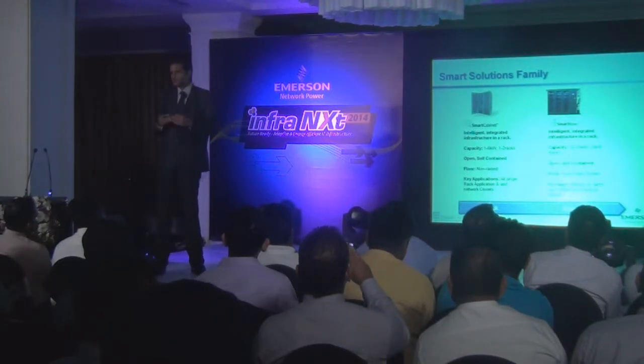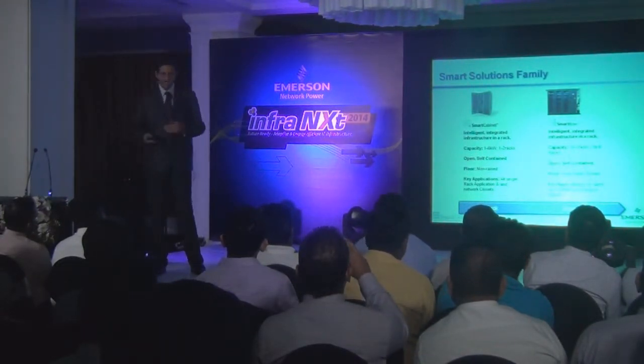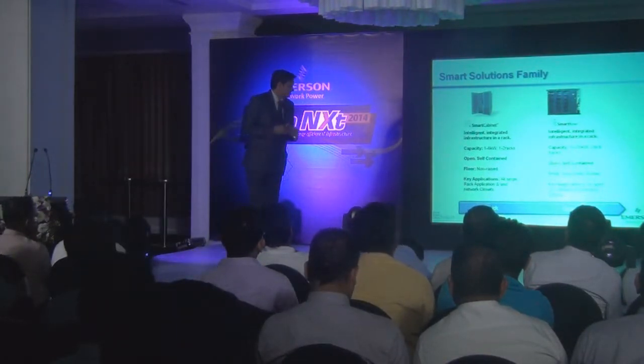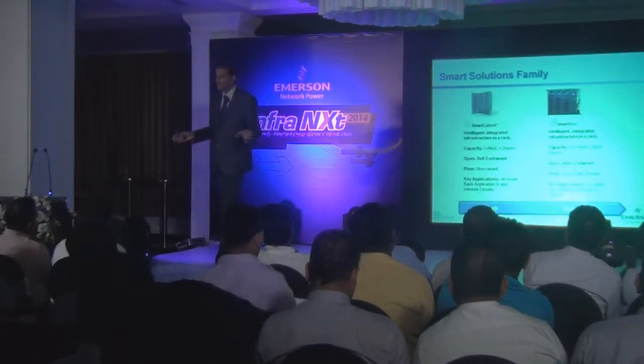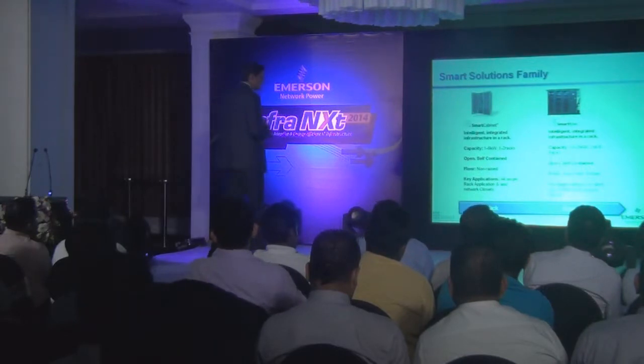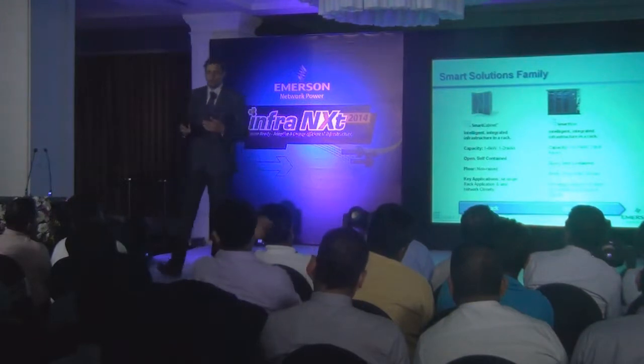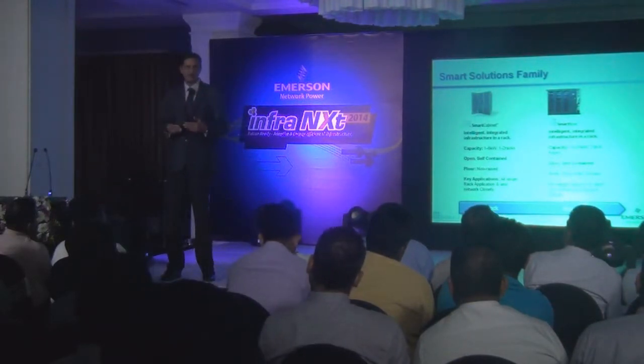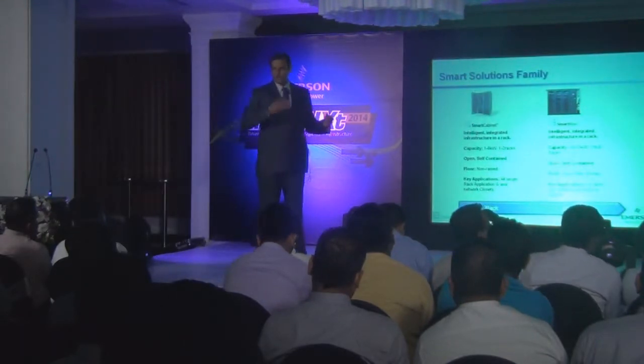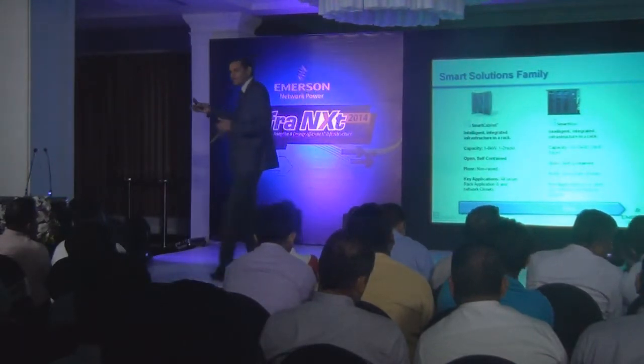It's a combination that starts from 3 and goes up to 6, and can be used in a very modular way. Here too, cooling is open and self-contained, and you don't need a raised floor since cooling is integrated into the infrastructure. The key application area is all sizes of data center. You can start operations with a 10 or 12 kilowatt load using smart row, and as your business grows, keep adding smart cabinets or multiple smart rows.